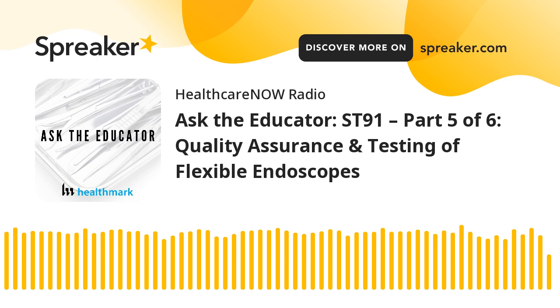And then we don't always have great lighting in our endoscope processing areas. And you have age as a factor in there for how much magnification you need and lighting. So it is just a quality practice to add in. If you're doing the inspection already, why wouldn't you do it under lighted magnification? And there are a wide variety of products out there, anything from a very inexpensive handheld magnifier through swing arm ones or desktop ones or microscopes. So we don't tell you what kind you have to use, but we do highly recommend lighted magnification for doing that inspection step that's required anyway.